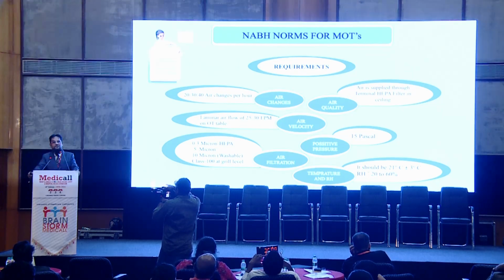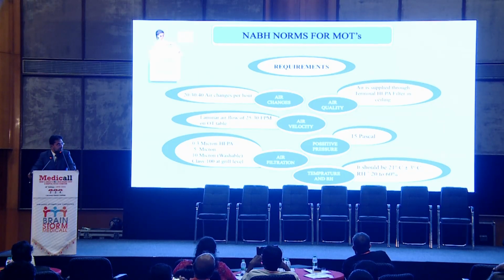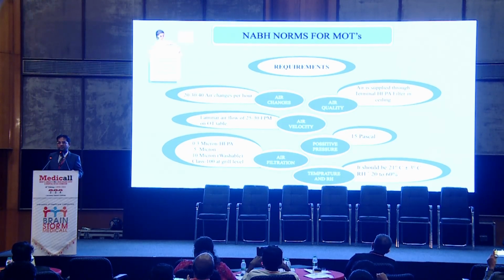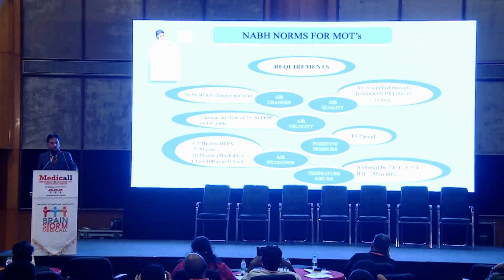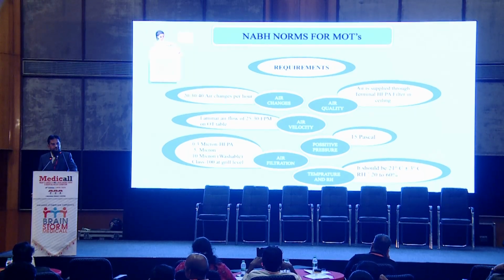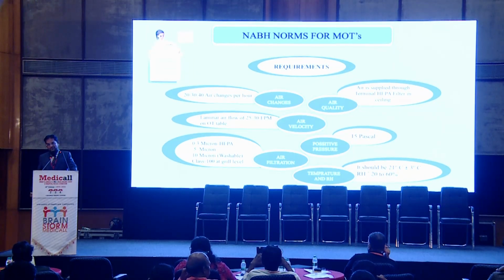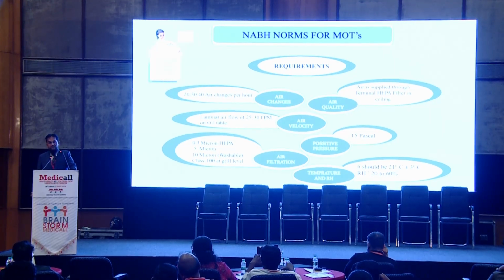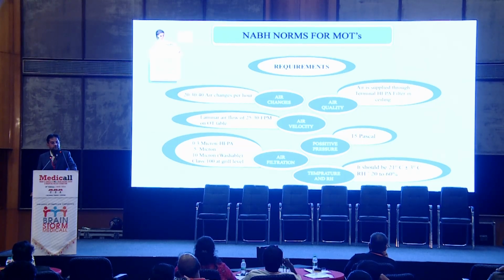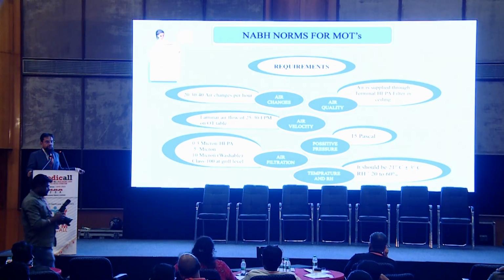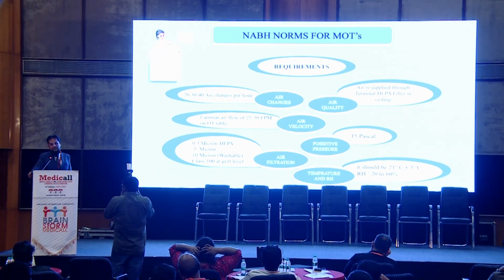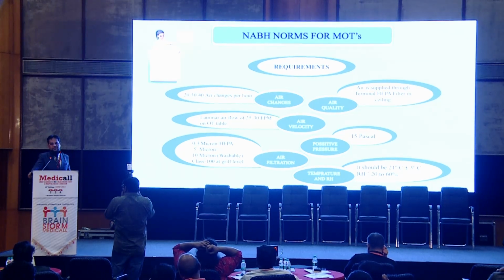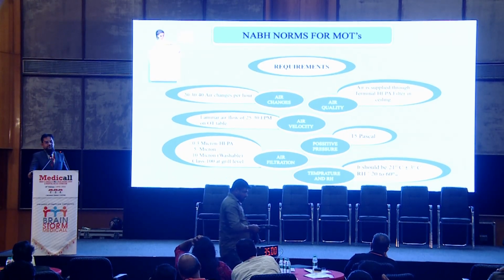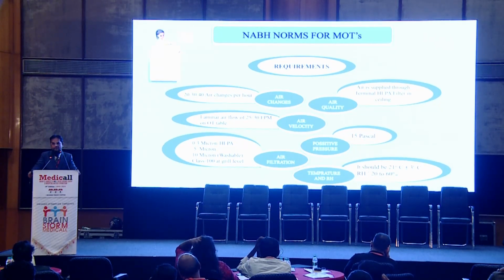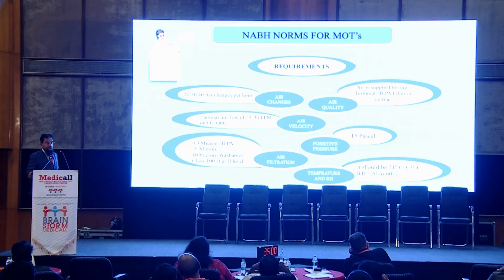Apart from that, they said that the terminal HEPA has to come through the ceiling. My system has that, because this is a ceiling suspended system. Then they said what airflow has to be maintained in an operation theater. Near the HEPA, it should be around 90 to 120 FPM, but at table level it should not be more than 25 to 35 FPM. That is maintained by our systems. They asked for a minimum of 2.5 Pascal, but our systems can give up to 15 Pascal positive pressure. Then the three-stage filtration they asked for, 0.3 micron, 5 micron, 10 micron. We have added one more, an activated carbon filter. And temperature, they said, around 21 plus or minus 3, and humidity between 20 and 60.